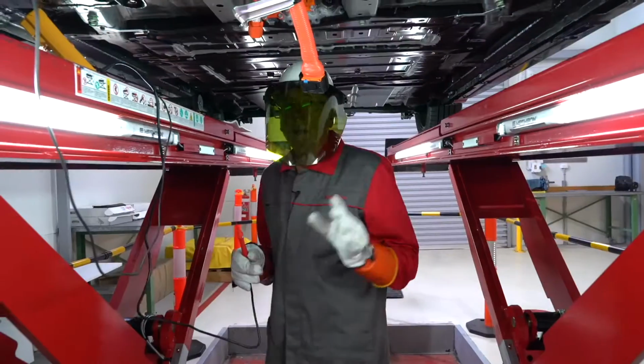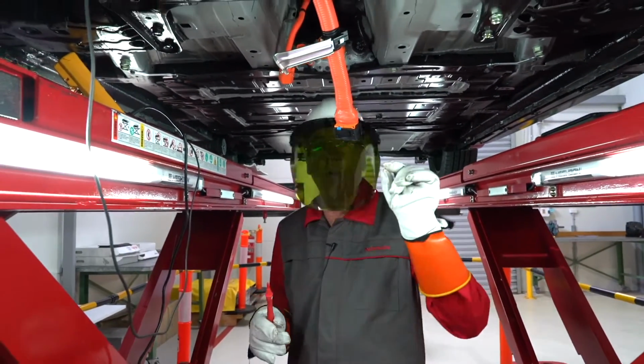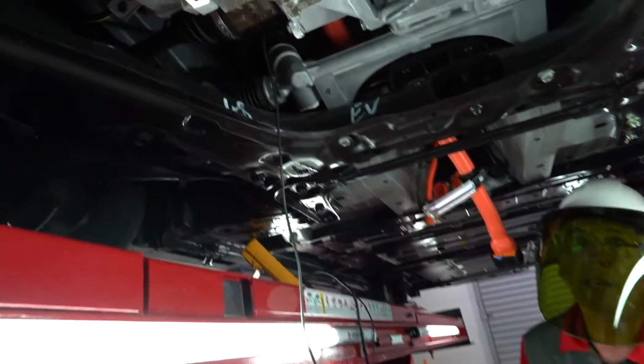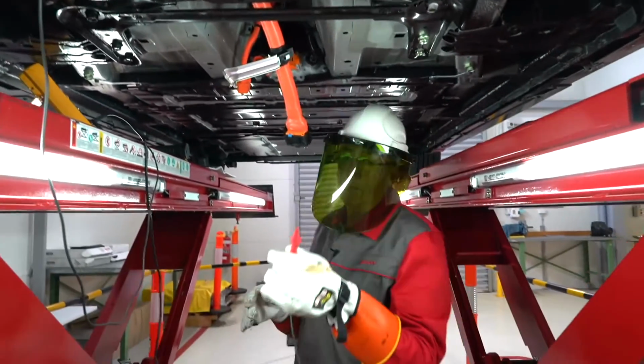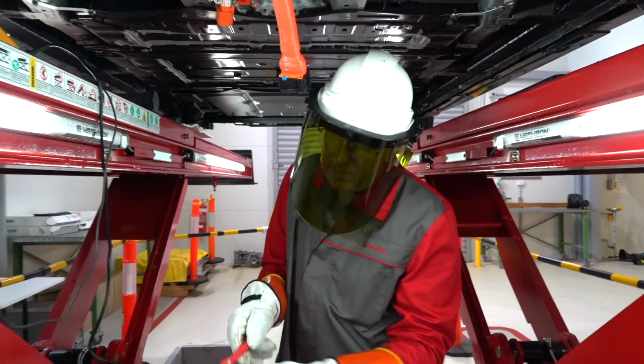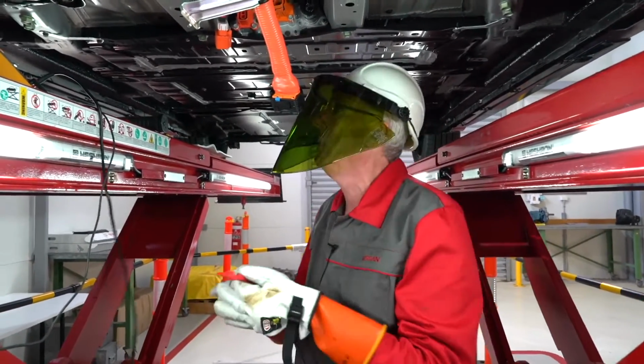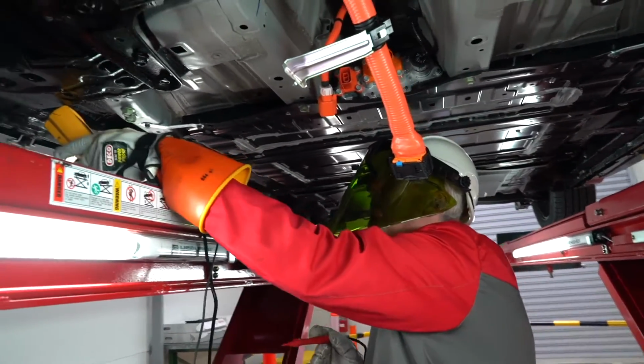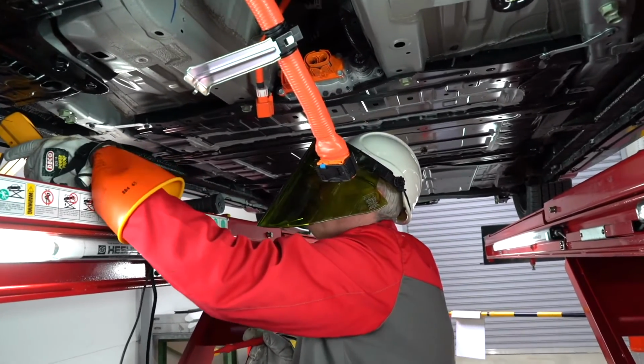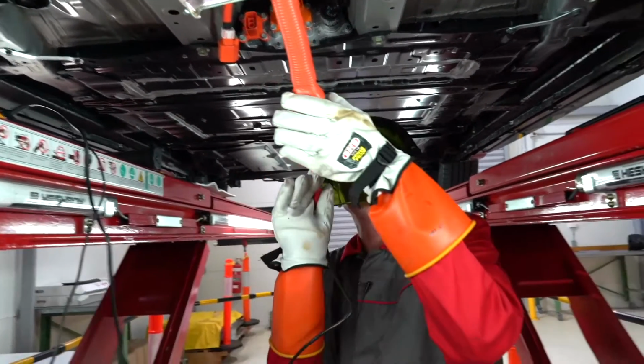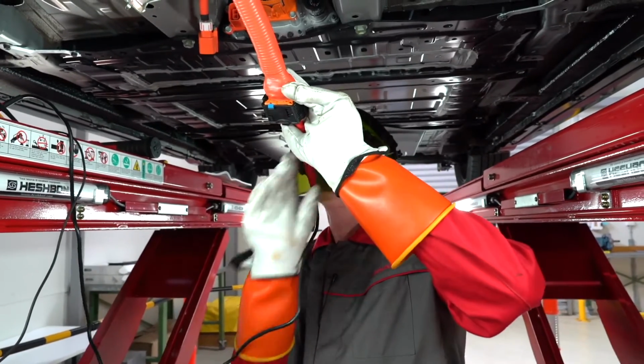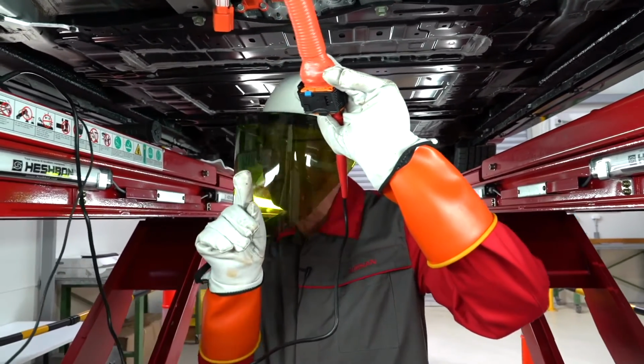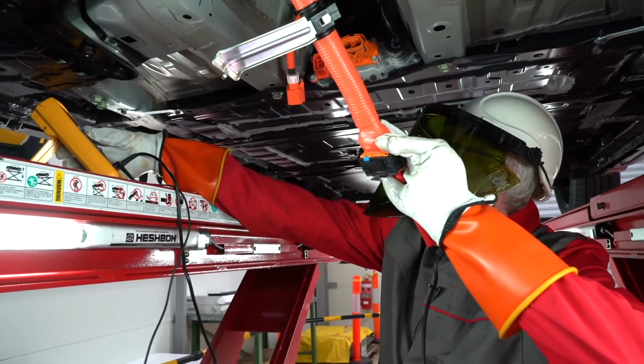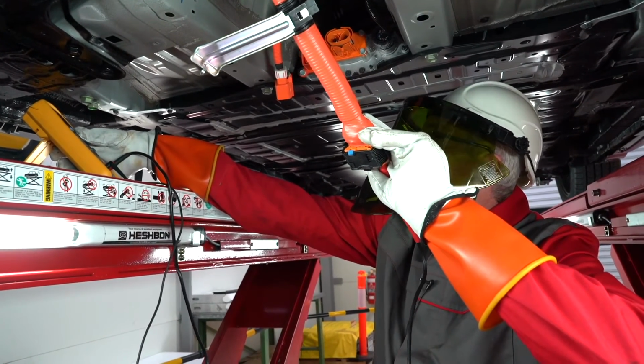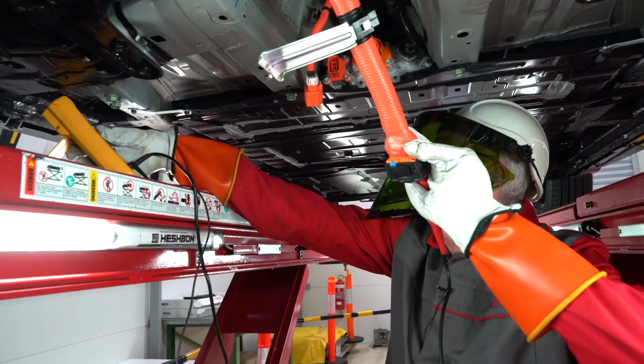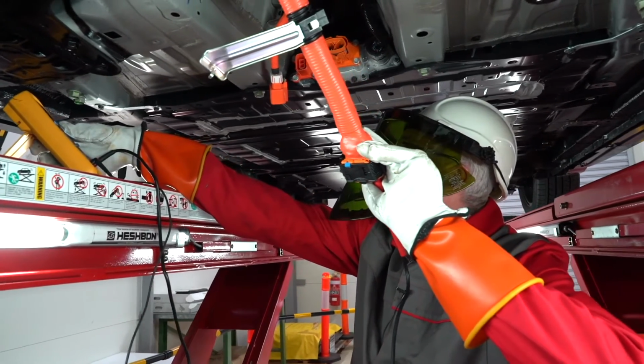Let's take a look. Okay, so what I've done here, I've connected my black crocodile lead up into the casing of the PDM, power delivery module. I've got my red lead here. I actually do have a test button on here, but I find it quite hard to push with my gloves on. So I'm going to use the test button of the actual insulation resistance tester here. I've set it to 500 volts. I'm going to go into the main spine here and hold it in. Remember, PPE, this must be done safely, very important. And I'm going to push and hold the test button.